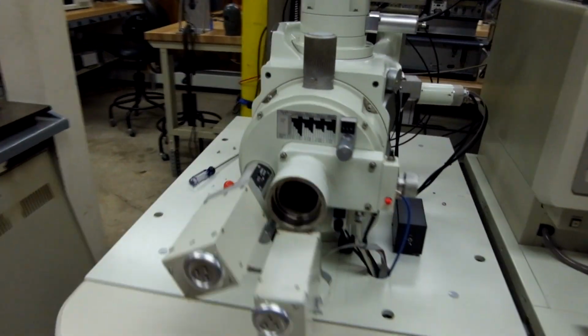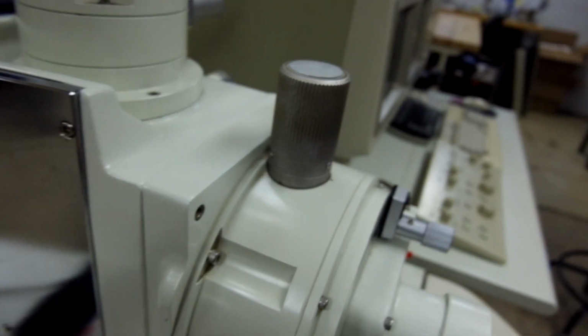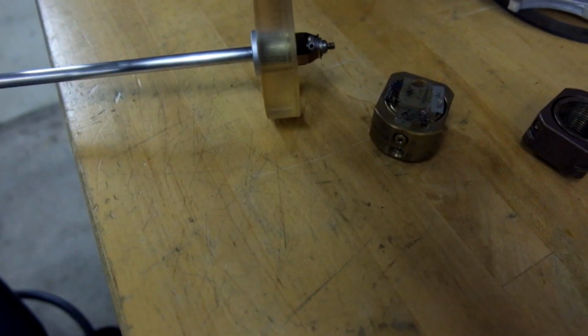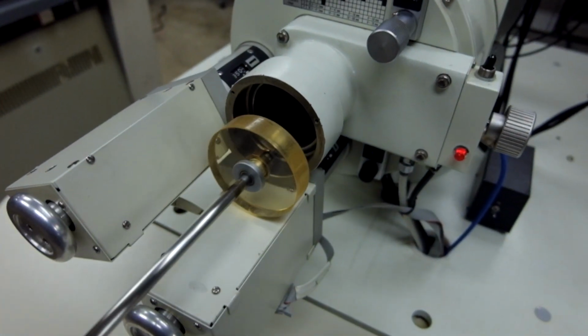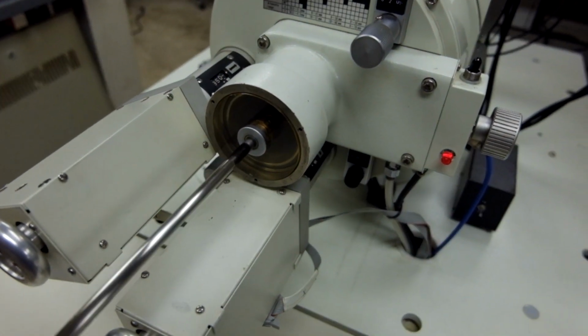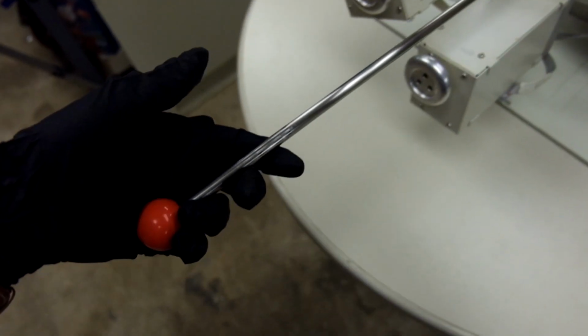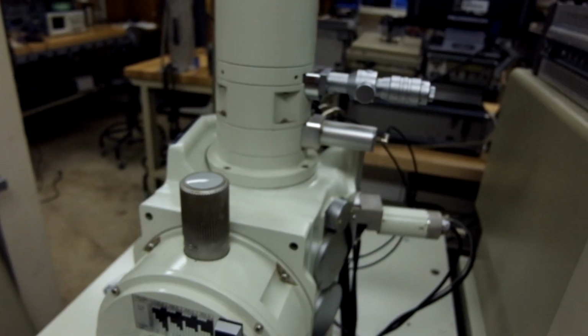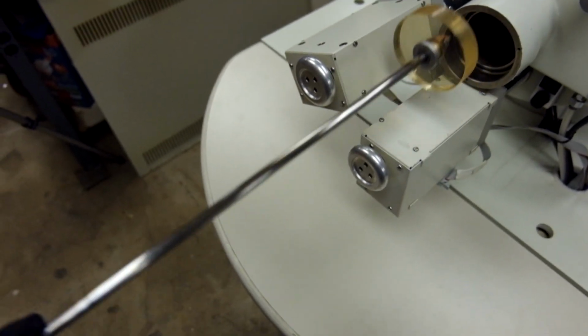So I want to show you how to load a sample the cool way. The less interesting way is using this thing here. You'll load your sample onto a sample holder or a pedestal like this, and the end of this rod will thread into it, and the rod will be inserted into the microscope like that. The airlock will be evacuated, and then you push this red ball all the way in there, and then you unthread the sample, so the sample stays in there and you can retract this and pull it out.